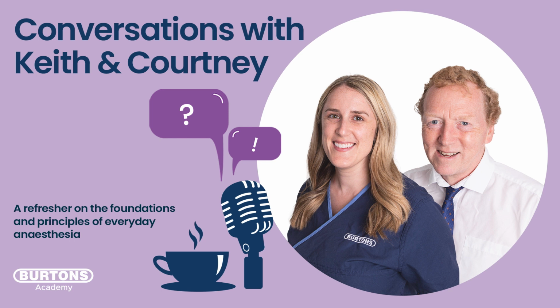Just to relate the two: as we start to breathe out, we've just breathed in, so our dead space is full of 0% CO2. Either we're in room air, breathing spontaneously, or we're on an anaesthetic circuit with a proper setup, so when we breathe in, there's fresh gas in our dead space. We start to breathe out, and all that fresh gas goes past the analyzer, whether side stream or mainstream, and appears as 0. Then as the alveoli start to empty and fill up the bronchioles, bronchus and trachea, we start to see the CO2.